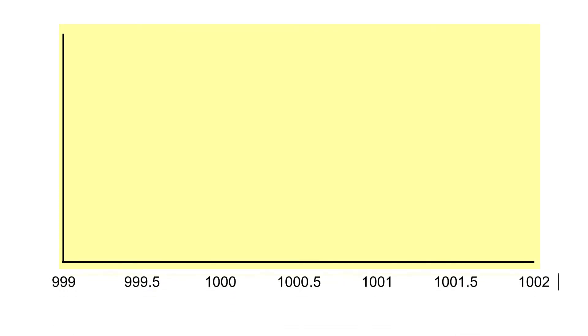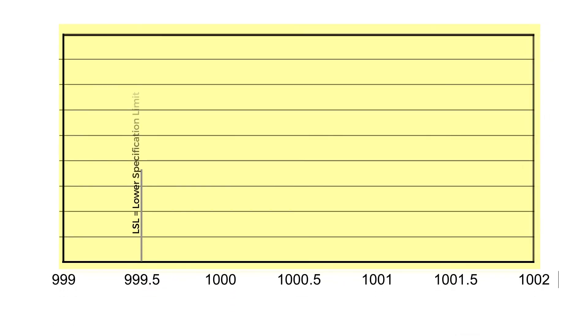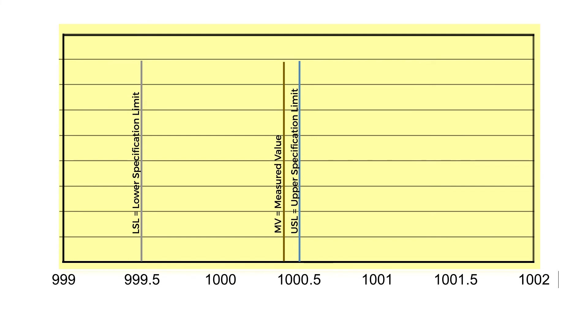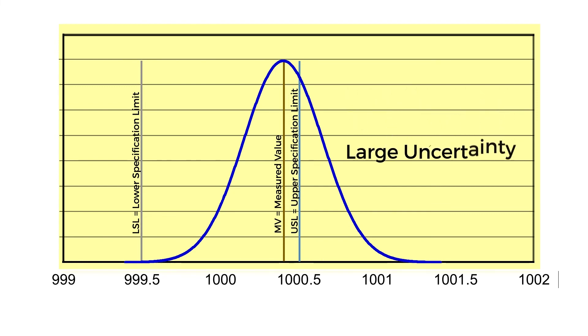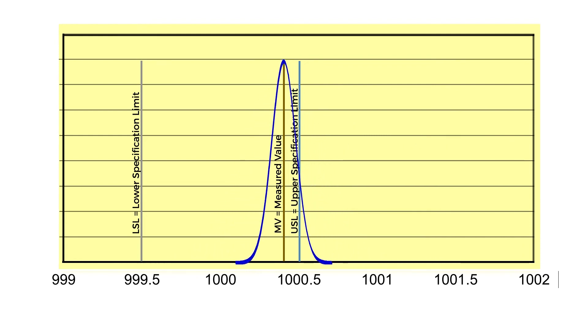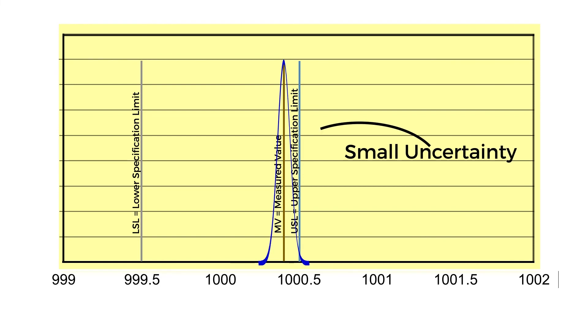When we use the appropriate formula and draw the concept, we draw the lower and upper specification limits at 999.5 and 1000.5. Next, we put in the location of the measurement at 1000.4. The calculated calibration process uncertainty determines the width of the distribution. As you can see, the larger the measurement uncertainty, the larger the risk relating to the measurement location. The smaller the uncertainty, the lower the risk, such as the case in this example when Morehouse performs the calibration.